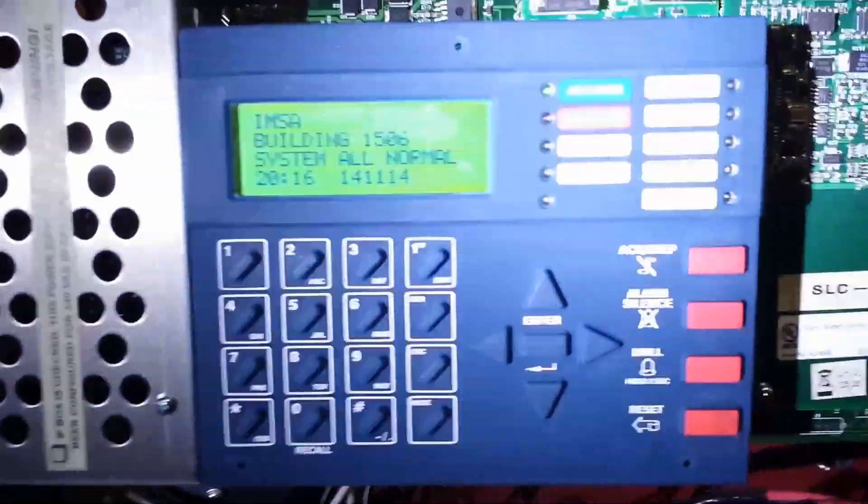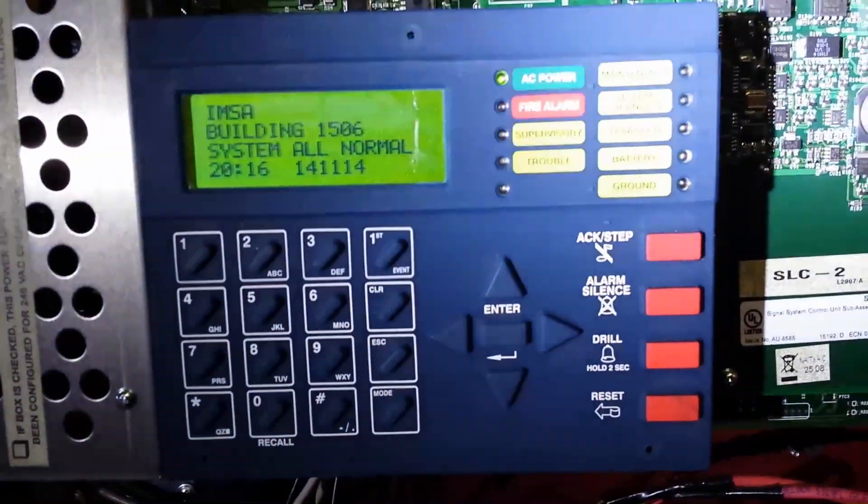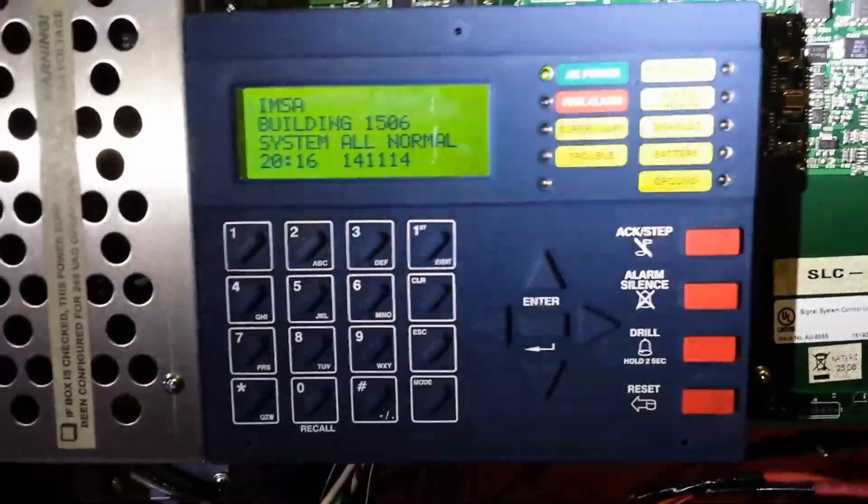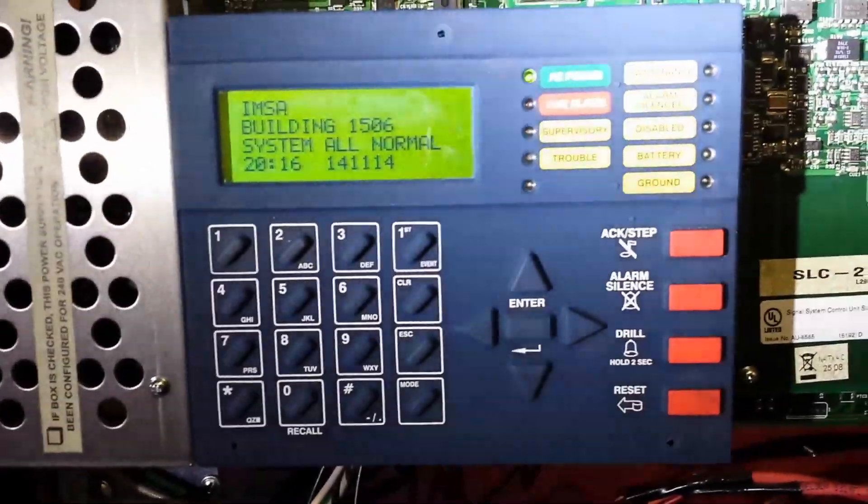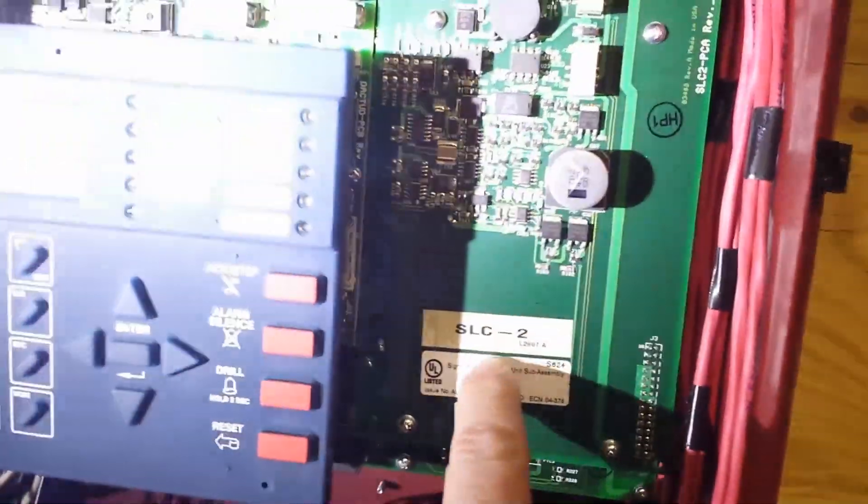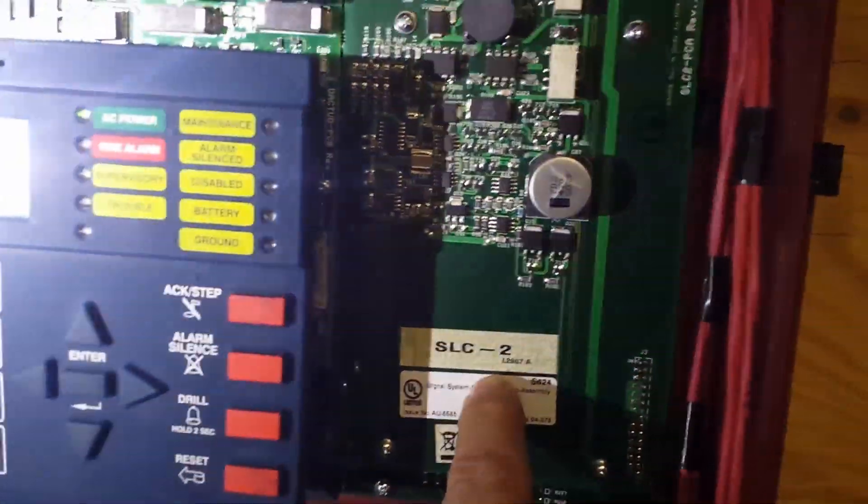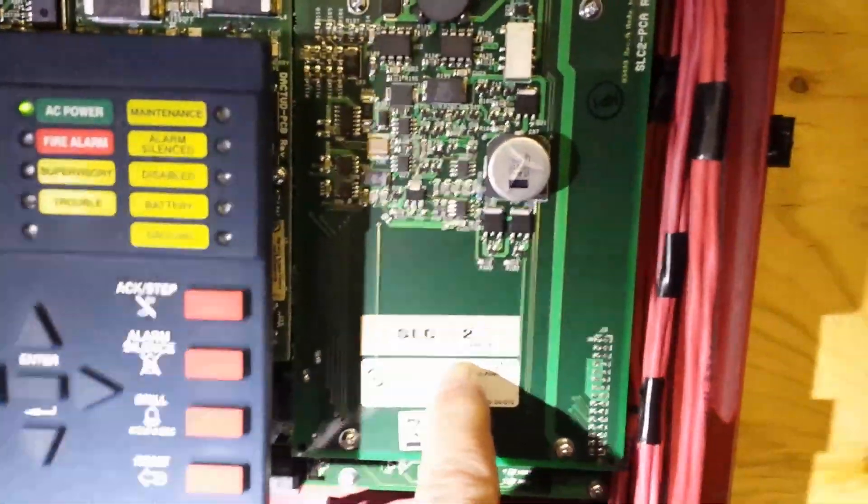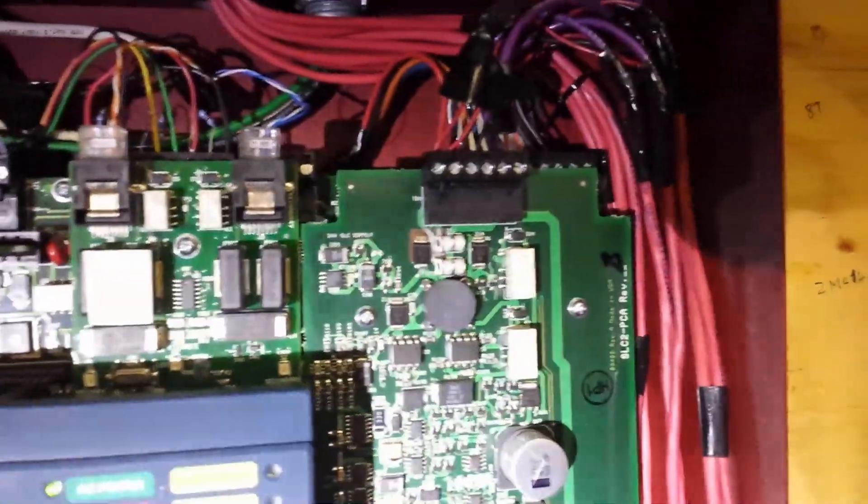Here's SLC2, wiring's connected, no problems. I'm fairly certain that if we do a hard reboot on this panel, it's going to come up and say initializing please wait, because that's what it did the other day. Something is going on. The other day we swapped this card from another building and it didn't seem to make a difference, so it's not the card.